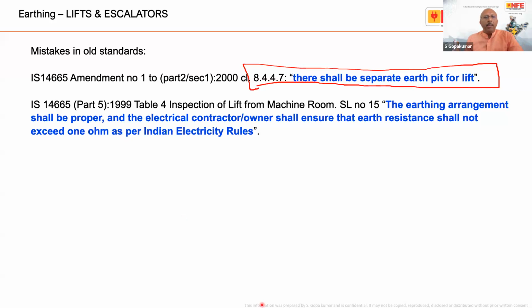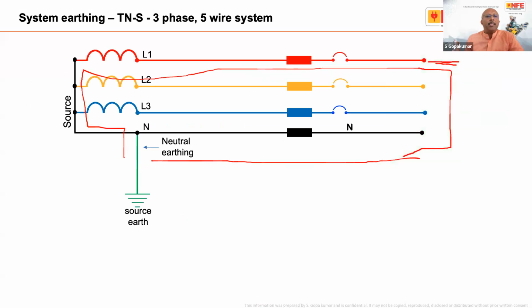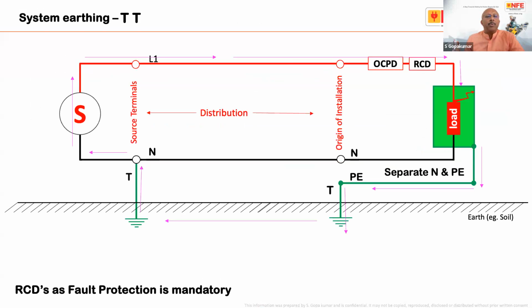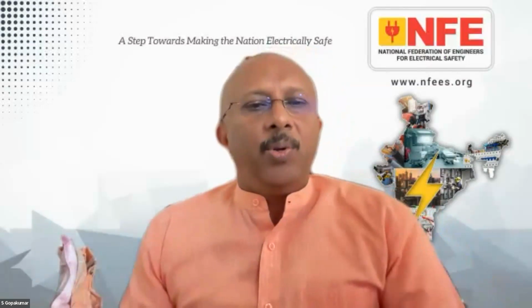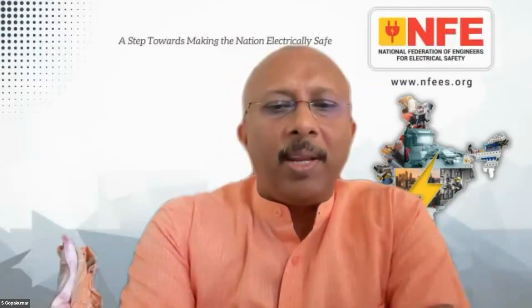So I hope the pictures are clear to understand what I am talking about. So this is a TT system. The TT system is not legal. You cannot use an RCD and operate a lift because it creates nuisance tripping. So that was my further explanation.